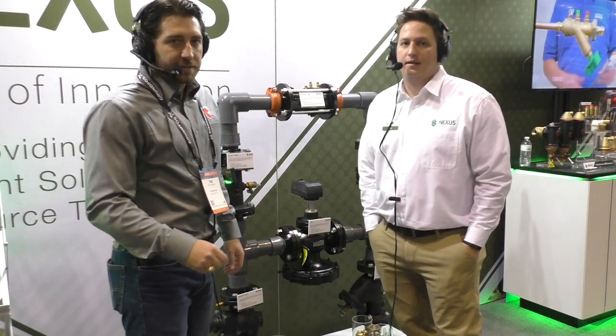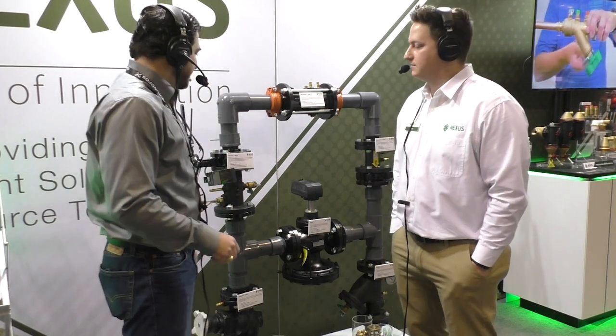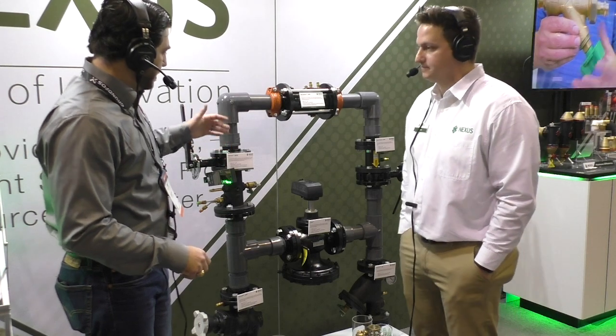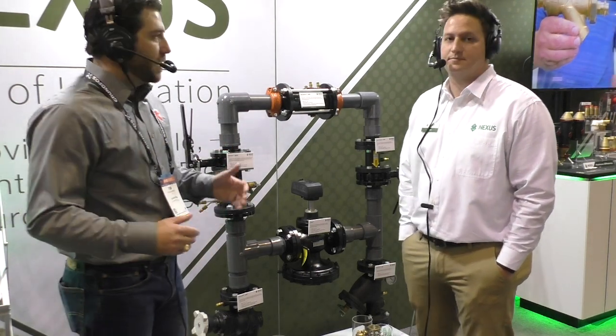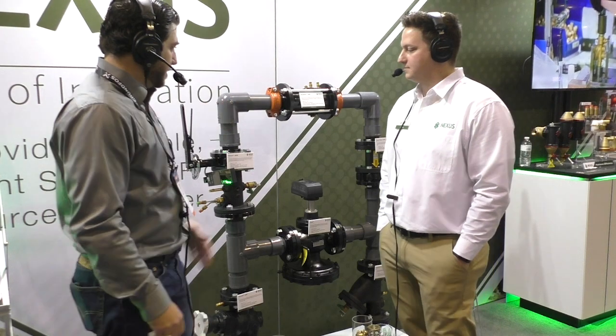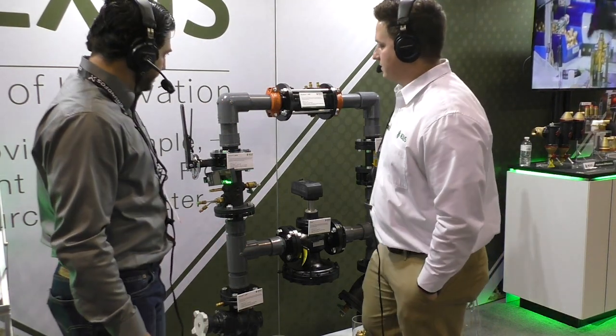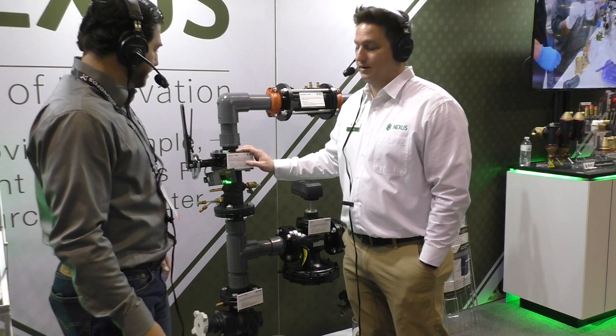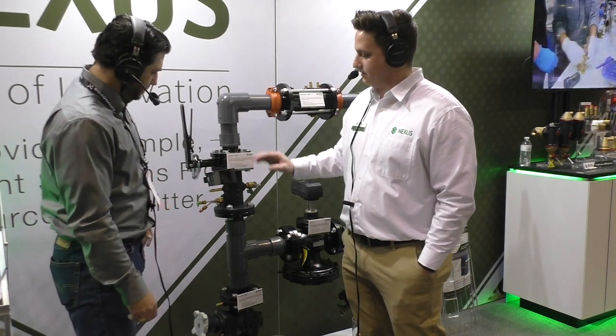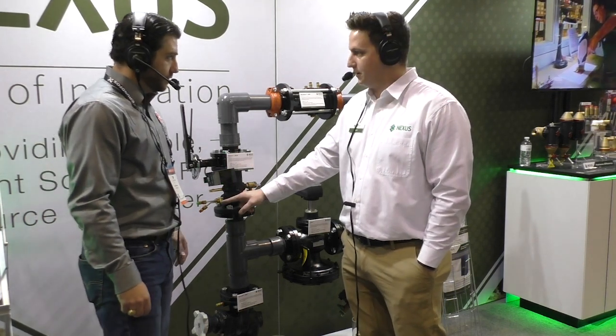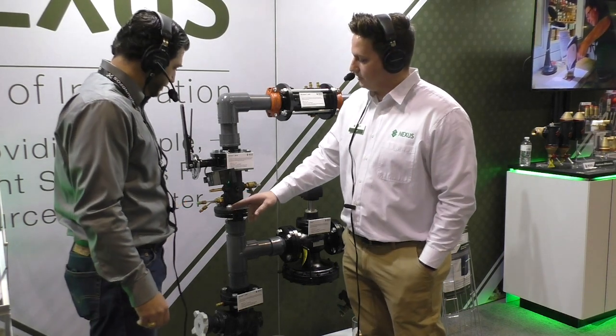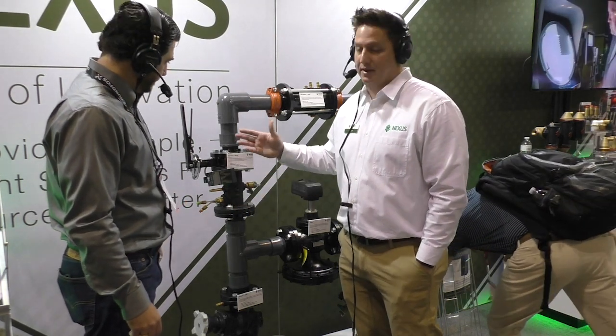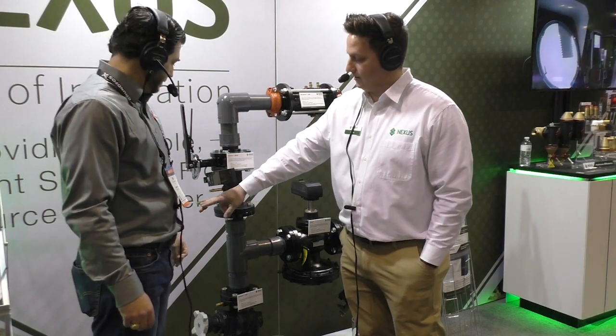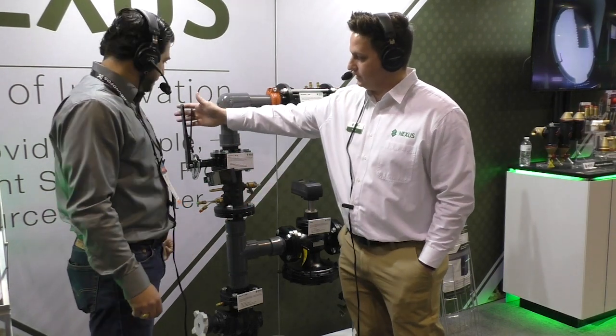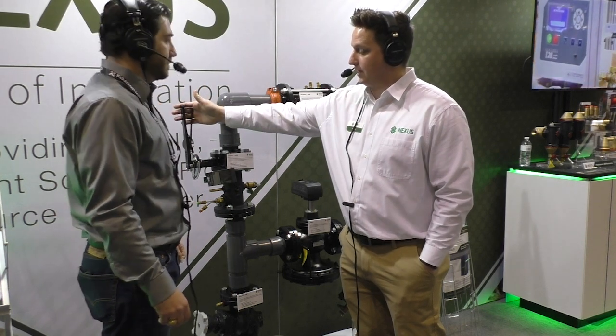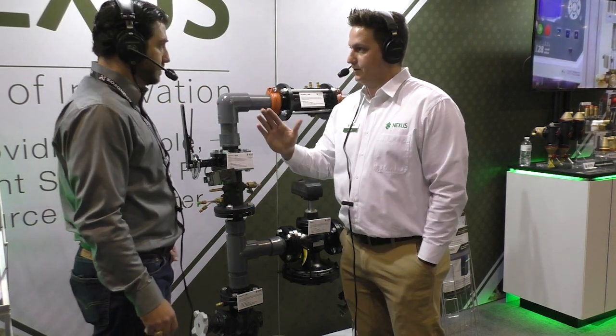All right. Now we are checking out some of the larger balancing equipment that Nexus has to offer. Typically, in this configuration, we're doing the NXFB balancing station. Would you give us a little info on that one? Yeah, so this is going to be an NXFB, and what that really means is you have a pitot tube here, which we call the twin tube. And so all you're doing here, it's just another way to balance in a system. You have your high and your low ports. You're adjusting with the butterfly valve here, and then you can really dial in your flow.